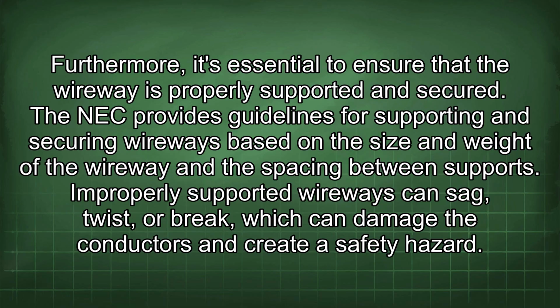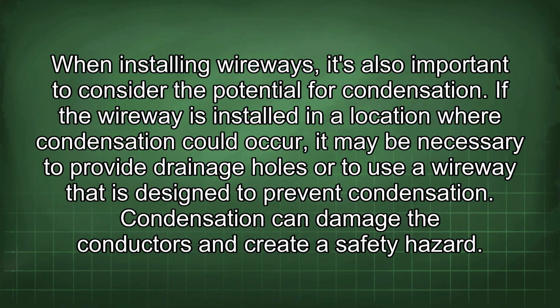The NEC provides guidelines for supporting and securing wireways based on the size and weight of the wireway and the spacing between supports. Improperly supported wireways can sag, twist, or break, which can damage the conductors and create a safety hazard. When installing wireways, it's also important to consider the potential for condensation. If the wireway is installed in a location where condensation could occur, it may be necessary to provide drainage holes or to use a wireway that is designed to prevent condensation. Condensation can damage the conductors and create a safety hazard.